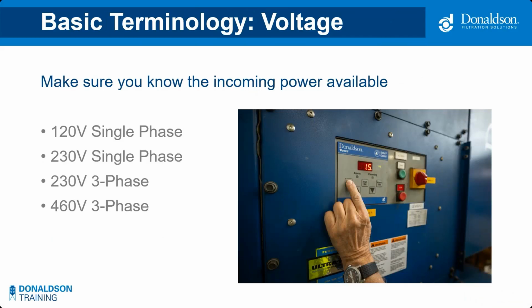And finally, we have voltage. We wanted to mention it, that it's really important that you make sure you know the customer's incoming power available when specifying electrical controls, both voltage and if it's single or three-phase power. It can be very costly and time-consuming to fix it if you don't identify it correctly on the front end.